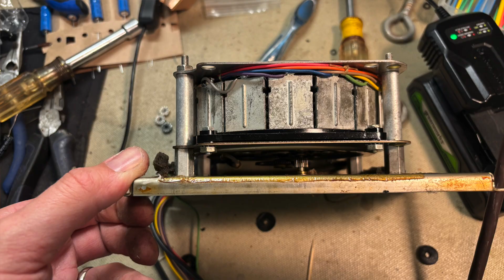When I took the cover off, I discovered that the scanner was absolutely loaded with dendrites, little fine crystals like metal hairs between all of the stators. And unfortunately, I couldn't remove the stators because they appeared to be riveted onto a plastic frame. So I tried to spray it down with contact cleaner and some compressed air, and when I reinstalled the scanner, I found that the problem actually got worse, not better.